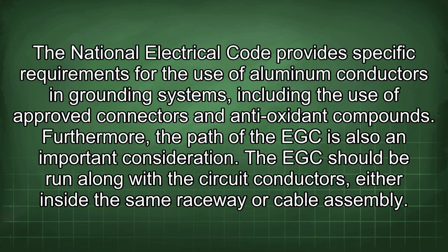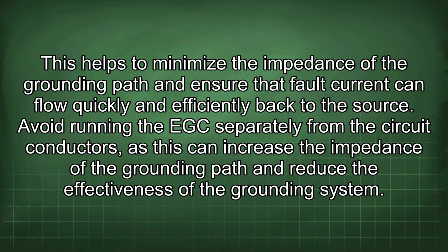Furthermore, the path of the EGC is also an important consideration. The EGC should be run along with the circuit conductors, either inside the same raceway or cable assembly. This helps to minimize the impedance of the grounding path and ensure that the fault current can flow quickly and efficiently back to the source. Avoid running the EGC separately from the circuit conductors, as this can increase the impedance of the grounding path and reduce the effectiveness of the grounding system.